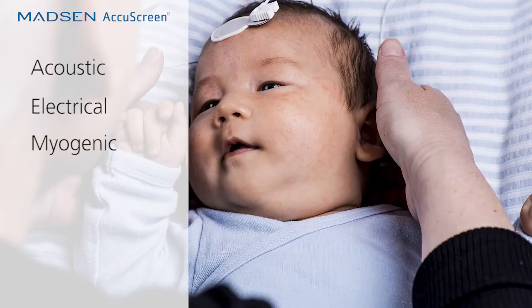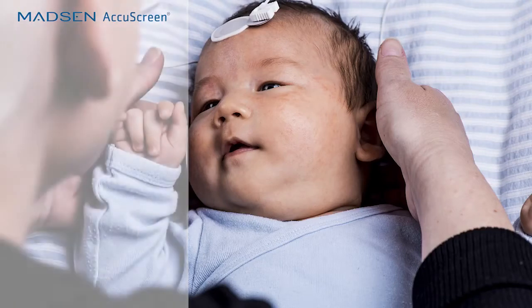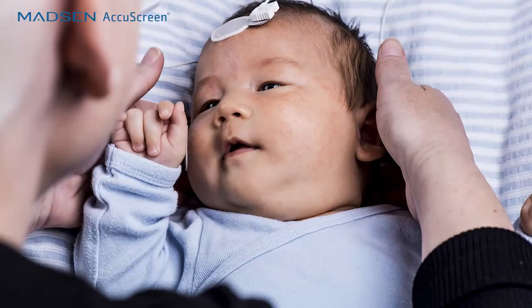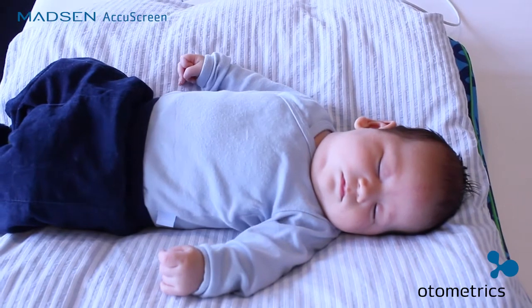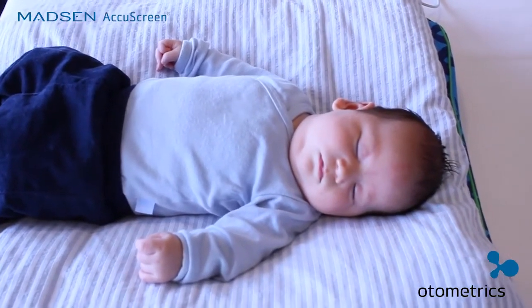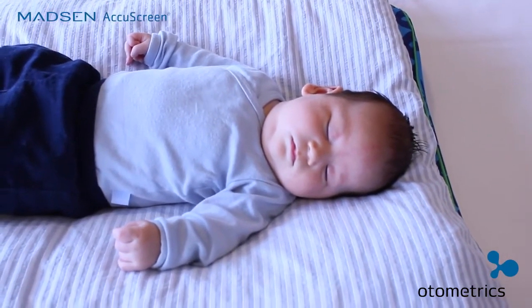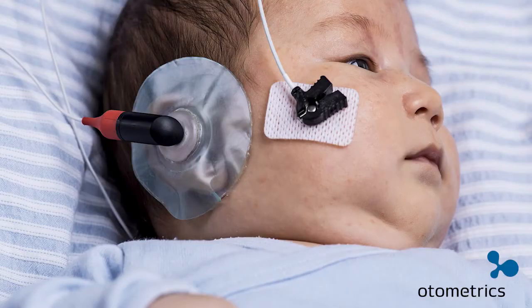when screening infants. Ask the people present to refrain from talking during the measurement and tell them to switch off all cell phones. If possible, perform the measurement away from noise sources such as ventilation ducts, buzzing or beeping computers, or other medical equipment. Also, close all open windows. To minimize myogenic noise, the baby should preferably be asleep. It helps if the baby has been fed recently. Remember that sucking on a pacifier generates a lot of myogenic noise. The test may take longer if the baby is restless, and this may result in a false refer.